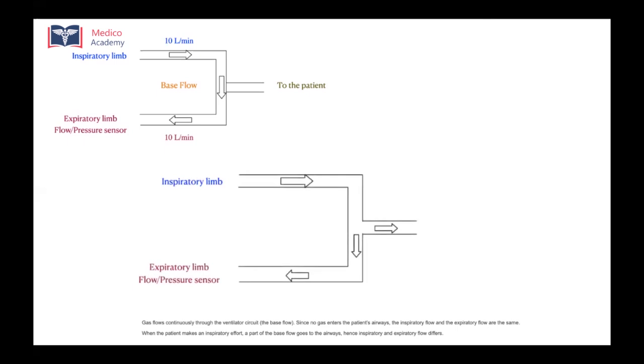So there is nothing going to the patient, right? At that time, since no gases are entering the patient's airways, whatever is coming from the inspiratory limb will go back to the expiratory limb. The inspiratory flow and expiratory flow will be the same, 10 liters per minute. But when the patient starts making an inspiratory effort, a part of the base flow goes to the patient. So inspiratory and expiratory flow will differ.